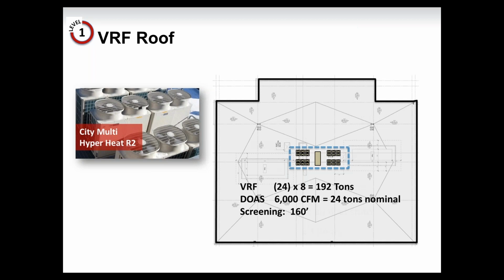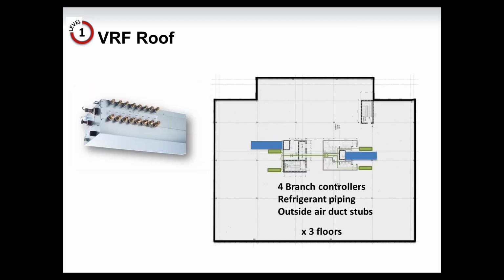However, this slide is showing that you'll only need 160 lineal feet of screening instead of the 350 required for the rooftop units. For the VRF design, we'll put 4 branch controllers on each floor and include all the refrigerant piping from those branch controllers up to the outdoor units on the roof. And then the blue is the outside air duct from the DOAS unit, just out into the ceiling plenum space for the return.